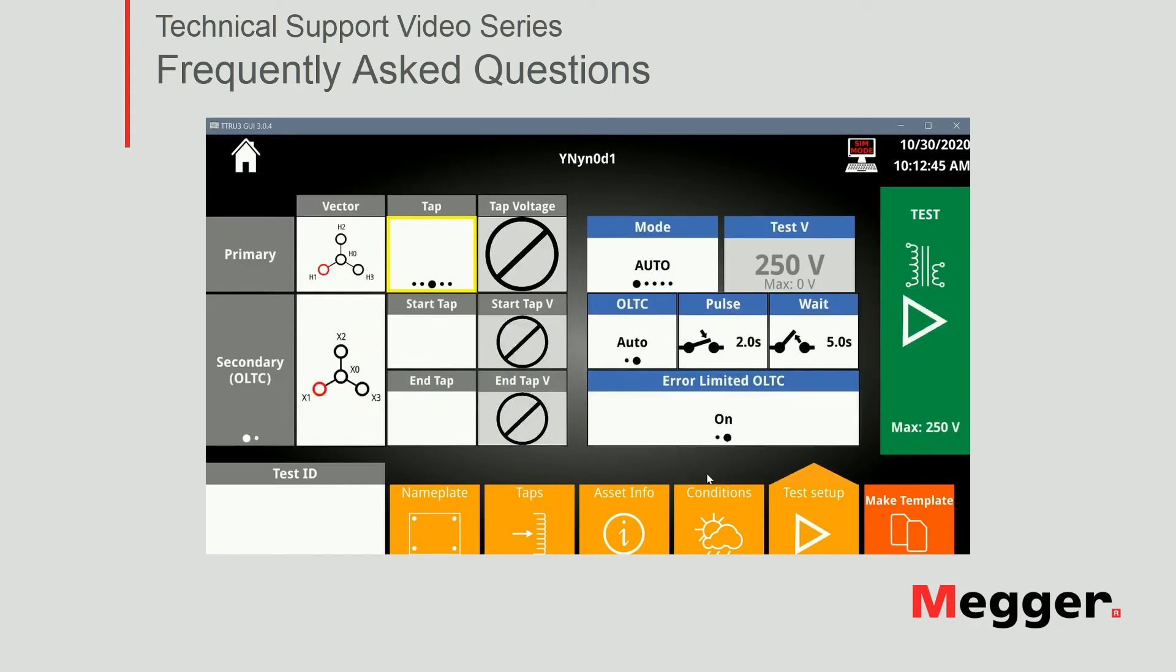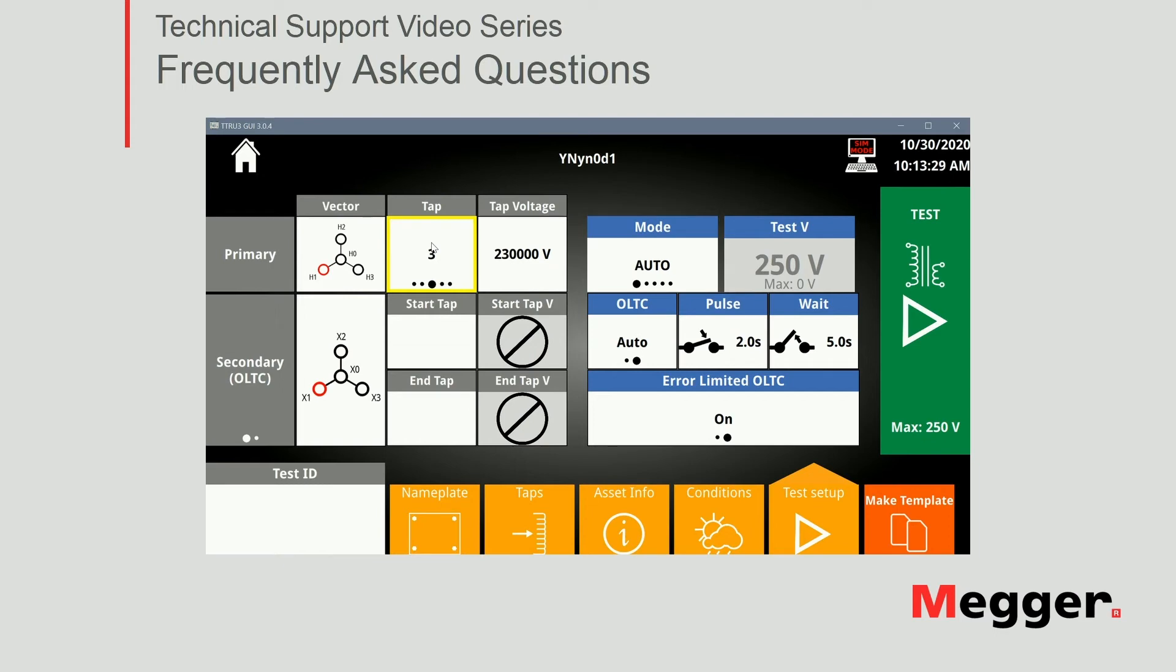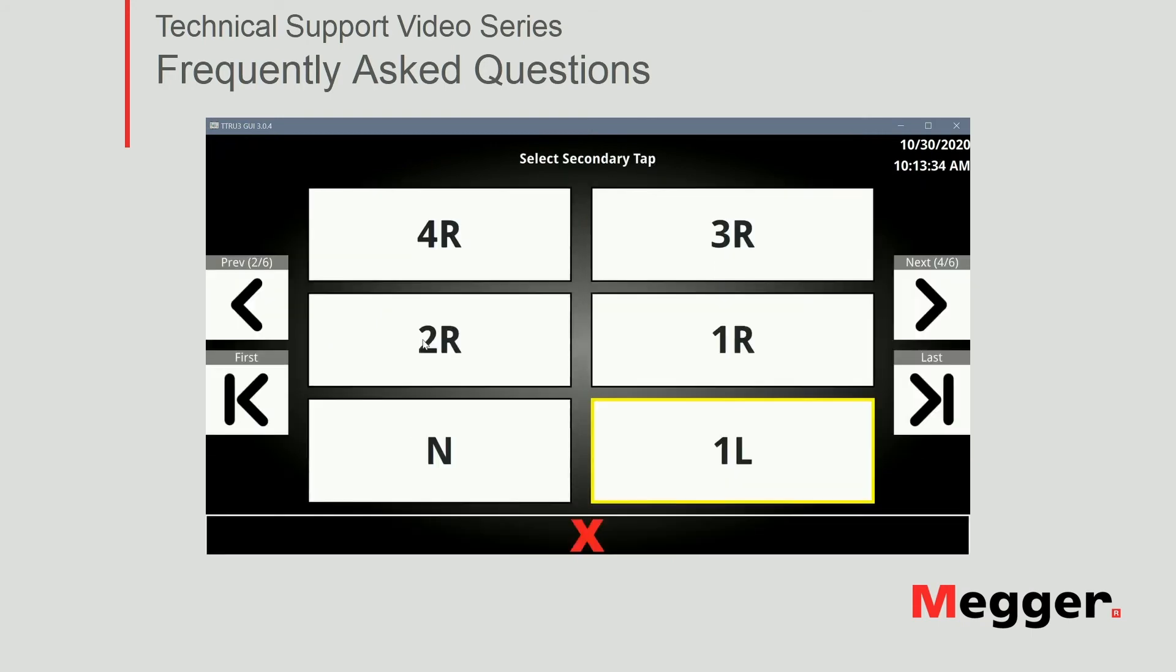At this point, we're ready to go ahead and go to my test setup. In this screen, we're gonna set up the first state of the transformer, right? And again, this video is about testing the on-load tap changer. So we're gonna just fix our primary on nominal voltage, right? Obviously, that's gonna vary depending on your case, especially if you're testing a transformer that's been in service for a long time. Typically, you can leave or you leave the primary on the service position and you test it that way. So again, on this example, I'm gonna select my nominal tap, which is tap number three for the primary.